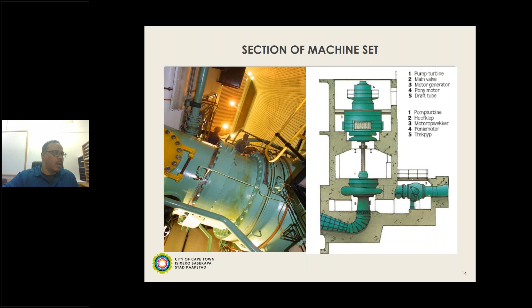The more important purpose of our pony motor is that at night, or when we are required to pump and send the water back up, we cannot rely on gravity. So the pony motor then has to run the rotor up to 600 RPM. It has to then start building up pressure against the MIV, or against the pressure or net head on the MIV. It has to then be greater than the head on the other side of the MIV. And then when that happens, we can overcome the downward force of the water due to gravity, and it will push it up, and then we start pumping up in the other direction.